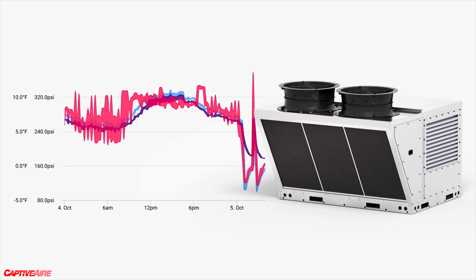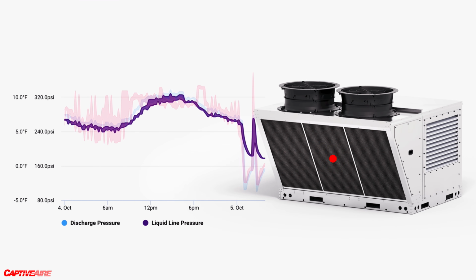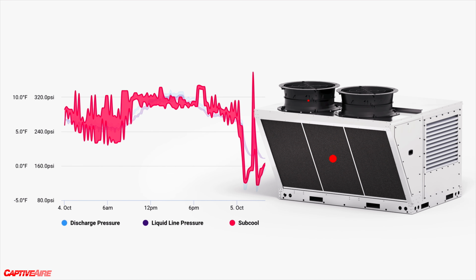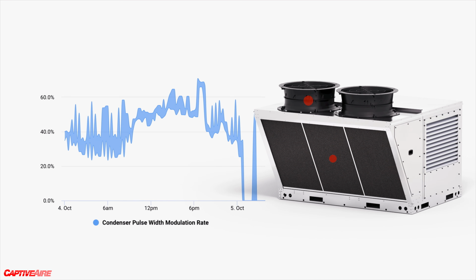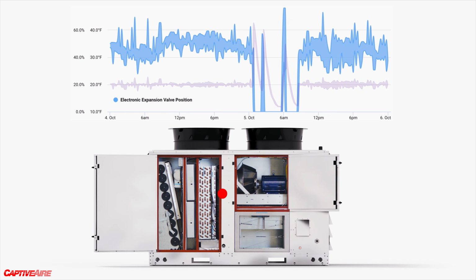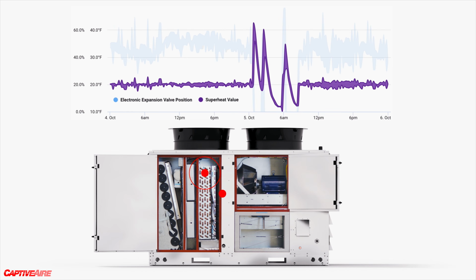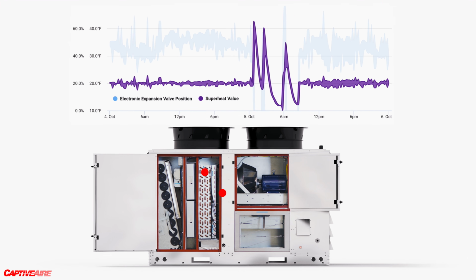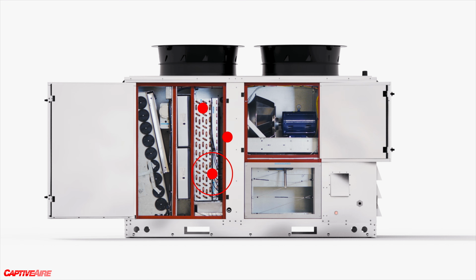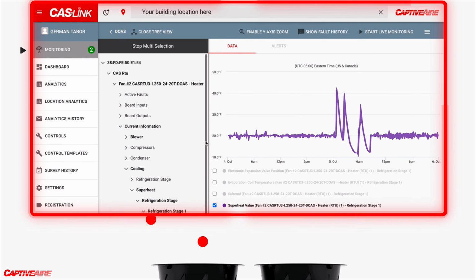Moving on to the condenser, we've got readouts for pressures and temperatures, including calculated values such as subcool, as well as monitoring and control of the condensing fan speeds. We can see the status of the electronic expansion valve and correlate that data to what's going on in the evaporator coils with live superheat readings. For precise humidity control, we measure the dew point right after the evaporator. Supply fan speeds and CFM are also displayed, as well as discharge temperature and humidity. Of course, we may also want to know what's going on outside if we're bringing in outside air. So we've got readings for outdoor air temperature and humidity, as well as the position of the outdoor air damper, which we can control. Again, these are just a few of the data points that come in through CASLink.